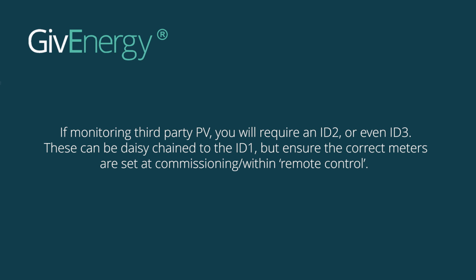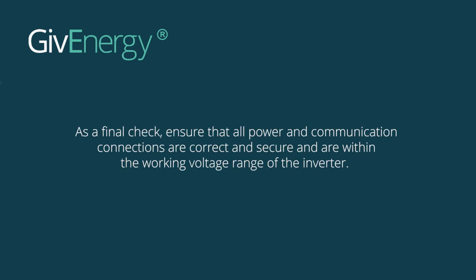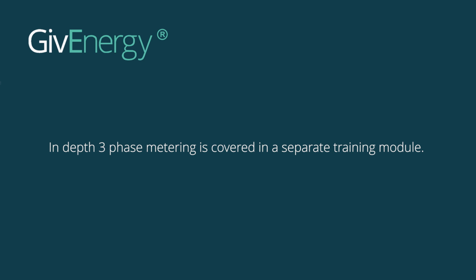If monitoring third-party PV, you will require an ID2 or even ID3. These can be daisy-chained to the ID1, but ensure the correct meters are set at commissioning within remote control. As a final check, ensure that all power and communication connections are correct and secure and are within the working voltage range of the inverter. In-depth 3-phase metering is covered in a separate training module.